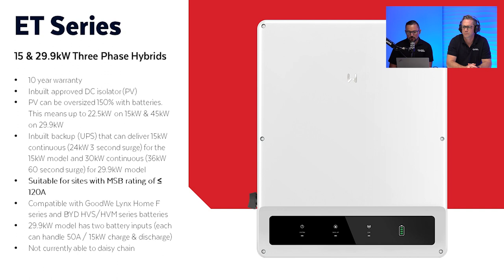At the moment, it's compatible with the Lynx Home F HV batteries, the stackable batteries from GoodWe, as well as the BYD HVS and HVM you'd be very familiar with, especially if you do a lot of Fronius. The 29.9 kilowatt model, interestingly, has two battery inputs, and each battery input can handle 50 amp of charge and discharge current. So if you're familiar with BYD HVS and HVM, you'd know you can parallel three stacks or towers together. Having the two battery inputs on that larger hybrid means you could parallel three towers into one input and three towers into the other.